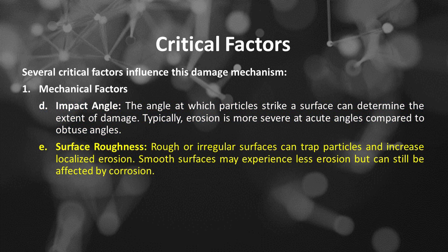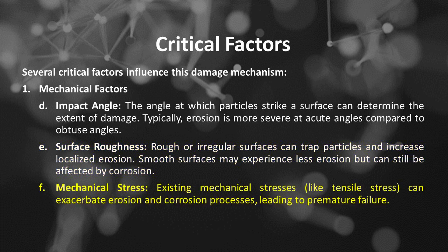The fifth is surface roughness. Rough or irregular surfaces can trap particles and increase localized erosion. Smooth surfaces may experience less erosion but can still be affected by corrosion. The sixth is mechanical stress. Existing mechanical stresses, like tensile stress, can exacerbate erosion and corrosion processes, leading to premature failure.